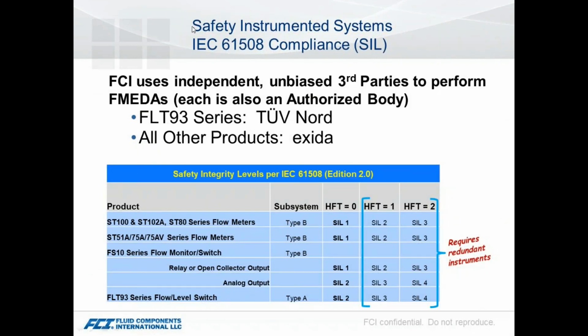As far as IEC 61508 goes, we have gone through a couple different partners, TÜV Nord and Exida, to get failure rate data on our products. So if you ever get into a safety instrumented system application, please don't hesitate to contact us, and we can see if we have a solution to meet your needs. For microprocessor-based devices, in a lot of cases a SIL1 is a single device. We do have a monitor, which we haven't talked about today. It's got a nonlinear output that reaches SIL2. And then our FLT93 flow switch, which we haven't talked about. It's a purely analog device, and it also is a SIL2 compliant device.